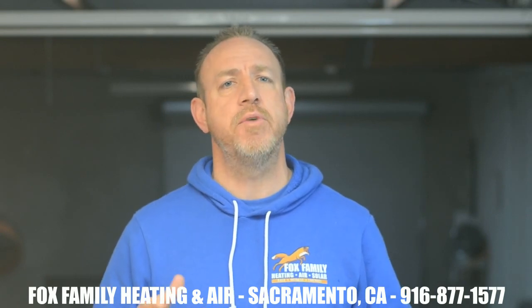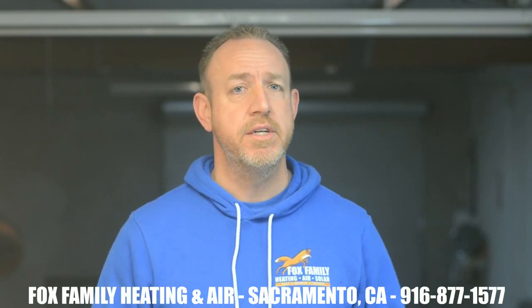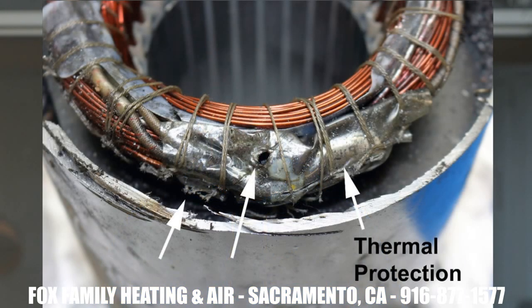Now let's talk about power surges. Asking questions with the homeowner can reveal a lot when diving into an HVAC system that isn't working properly. A recent thunderstorm or lightning strikes in the area can send a surge through the house's electrical system. That surge might not affect the lights or kitchen appliances, and may not even trip the breaker at the main panel, but it might take the transformer out before the board, sending a jolt onto that sensitive control board. Brownouts from the power company are notorious for damaging HVAC equipment — a reduction in power that suddenly comes back on with no warning could damage protective coatings on parts, causing them to fail either now or a couple years from now.